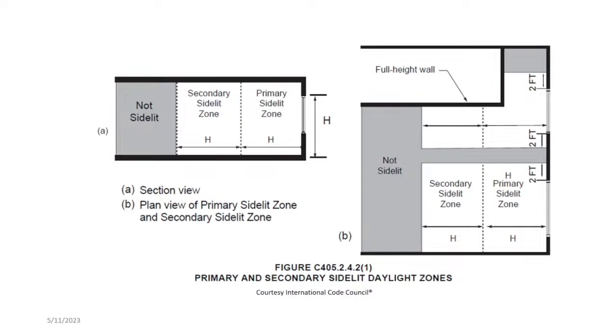The other big problem that we're having, and Title 24 is the first code that actually addressed it, is that in this room you've got 2x4 troffers, but more and more what we're seeing is linear LEDs that would basically start over here and go 16 feet. It's a continuous fixture with a single driver. And they'll say, oh, we'll do a better job, we'll control that whole fixture as if it's in the primary zone, we're gonna save more energy. Well, the problem with that is after the first couple months, they disconnect the photocell, because as you transition between the primary to the secondary and then to the non-daylight zone, each of those transitions, your light from the outside drops off about 20%. So by the time you're all the way in the non-daylight zone, you're 40% lower, but you've got a light that's dimmed down for the primary zone.